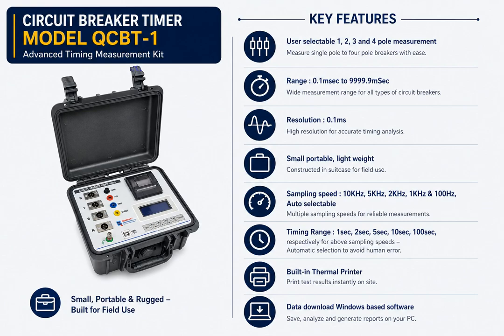Here are some of the main features of the Breaker Timer Kit. Most importantly, we offer user-selectable 1, 2, 3, and 4-pole measurement. Range: 0.1 millisecond to 9999.9 milliseconds. Resolution: 0.1 milliseconds. Small, portable, lightweight, constructed in a suitcase for field use. Built-in thermal printer to print test results. Data download with Windows-based software. Sampling speed auto-selectable to avoid human errors.